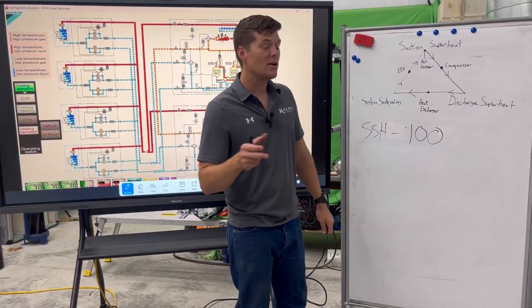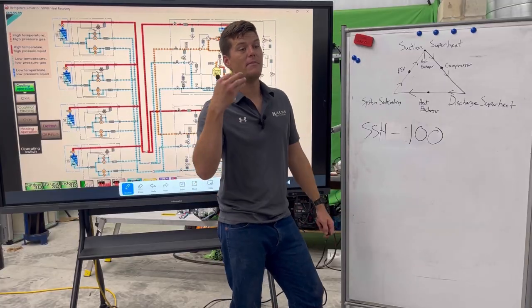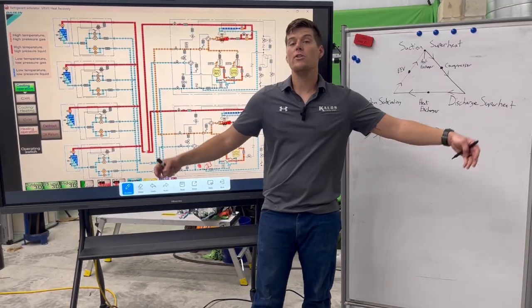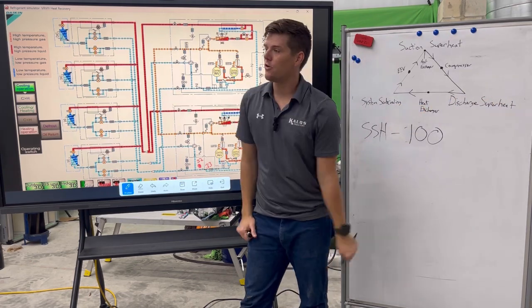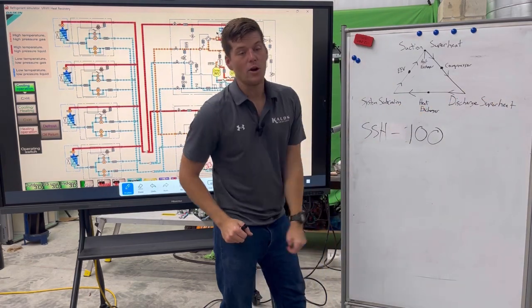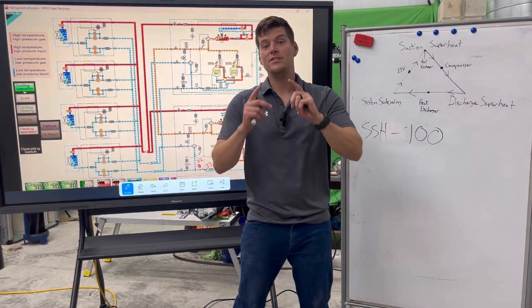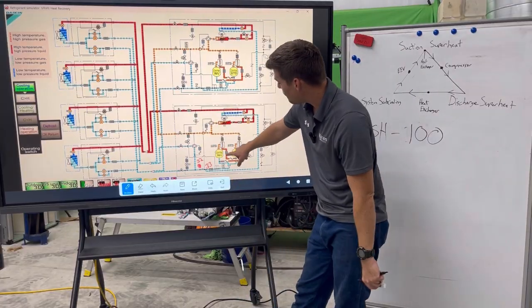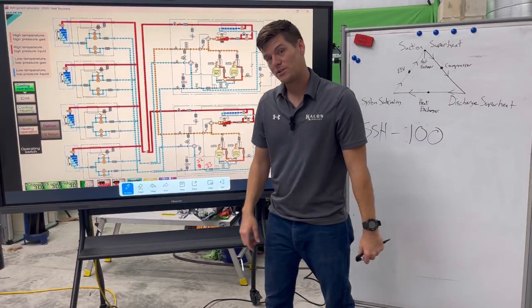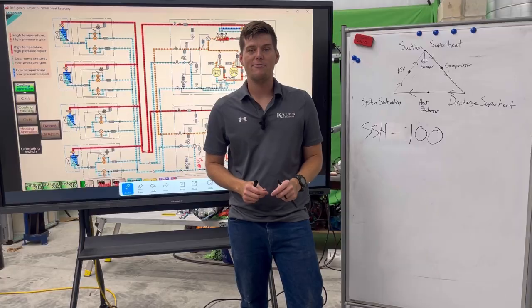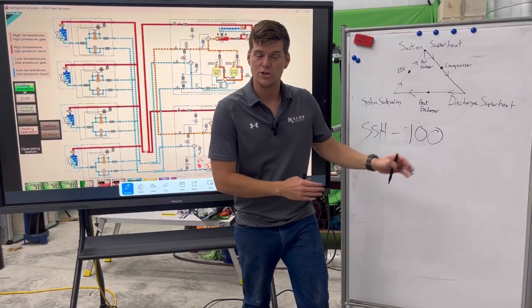Now, VRF is a little bit different than other air conditioning systems. You're going to find manufacturers for residential equipment where they'll say that 15 degrees is great, or 20 degrees is great, or 25 degrees is great. The difference is this beautiful thing right here. It's the compressor. Every compressor is manufactured to handle a different type of suction superheat.